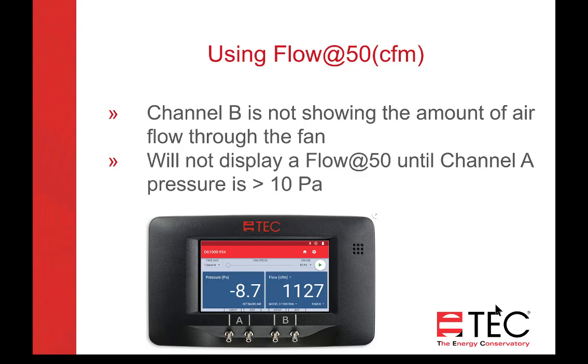So now we can see we're at 1127 CFM at negative 8.7 pascals. So now we can see that flow. So we can tell we've got way too leaky a house for ring B. In fact, we're gonna need open fan. So either this house isn't as tight as you thought, or a door blew open, or a window's open, or something's going on. Side attic hatch popped open.